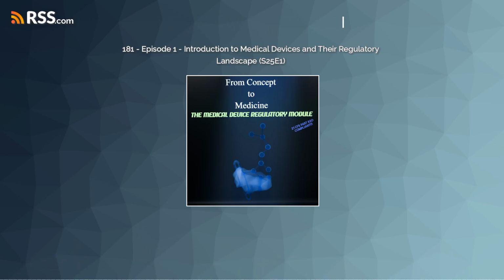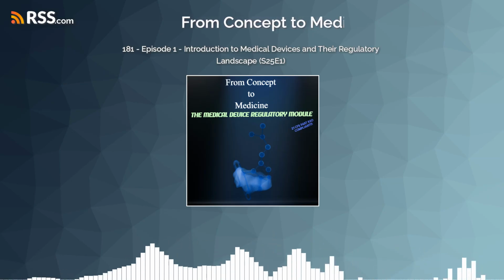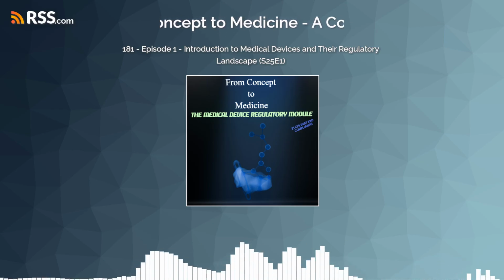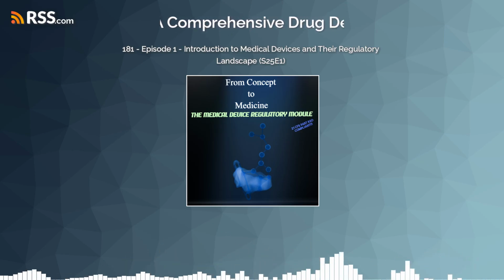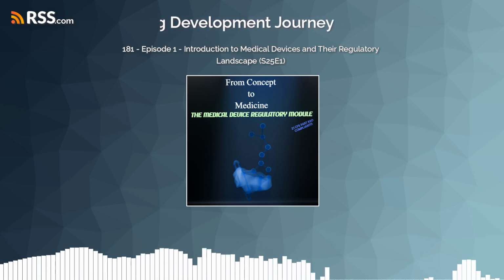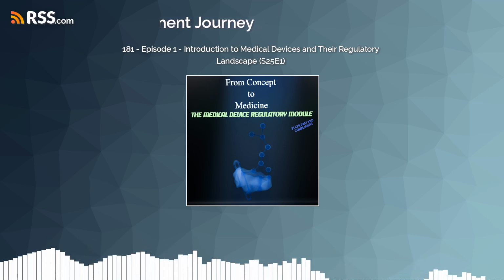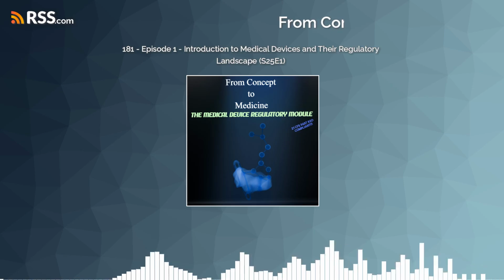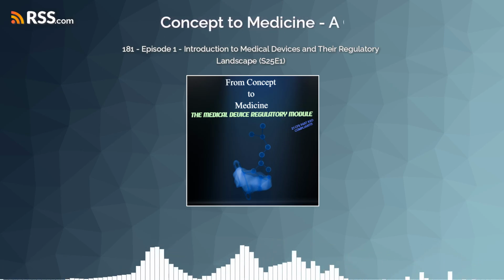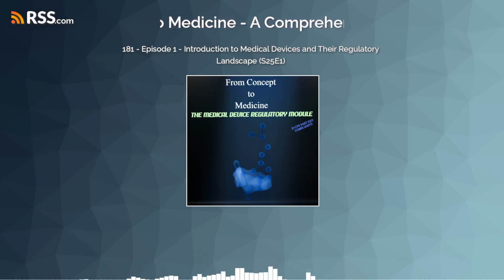Right, high stakes. For these SR studies, the sponsor or investigator must submit an IDE application directly to the FDA and get approval before starting the study. It's a very high bar, involving detailed protocols and safety monitoring plans. And if it's not a significant risk device study, a non-significant risk, or NSR, then the study is considered to have IDE status without formal FDA submission, but it still requires approval and oversight from an institutional review board, or IRB. The IRB still plays a crucial role.